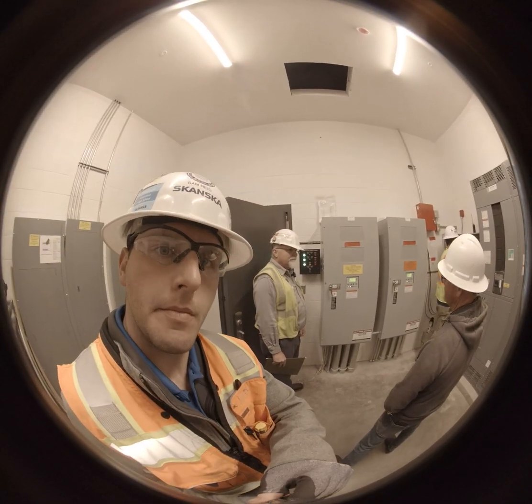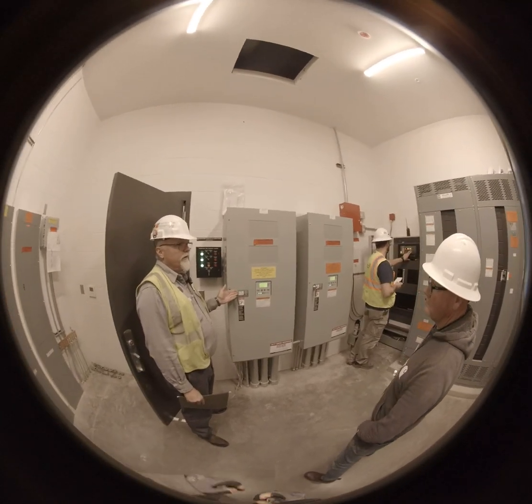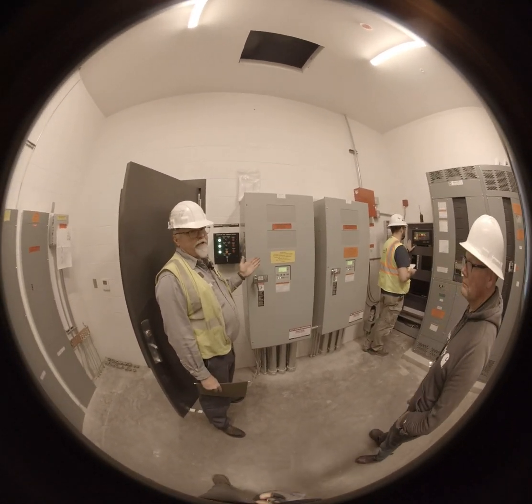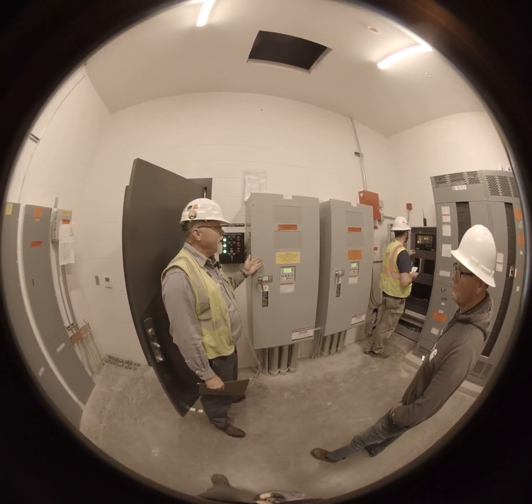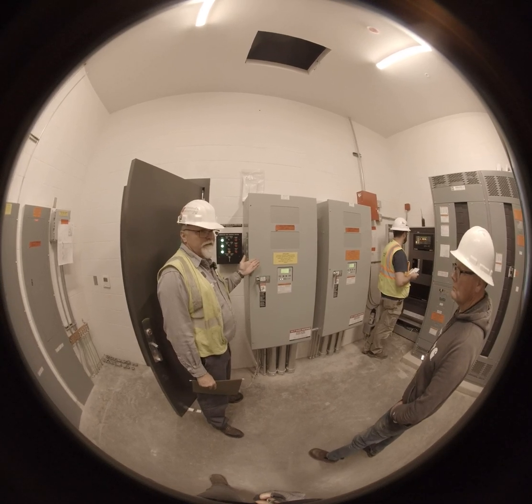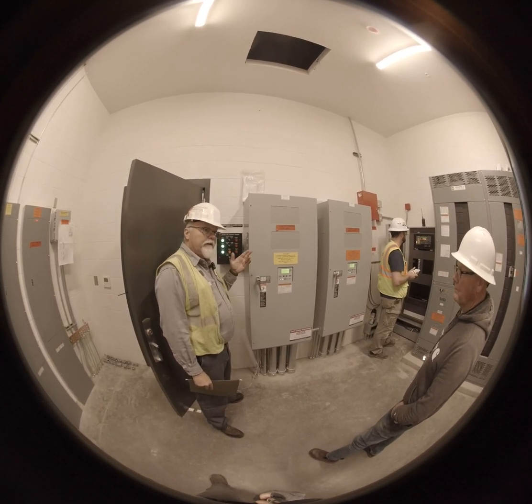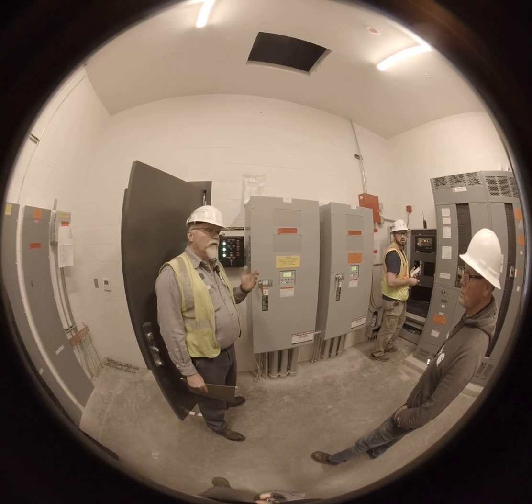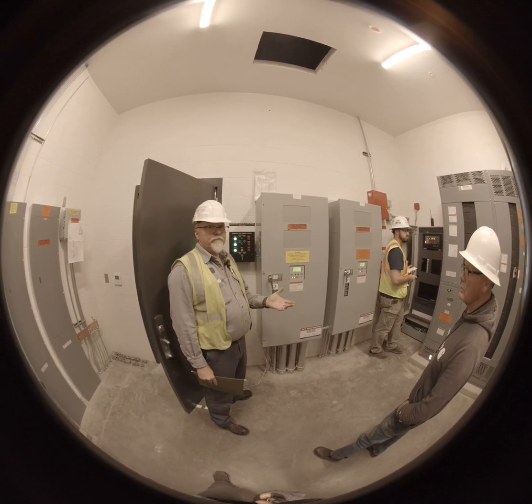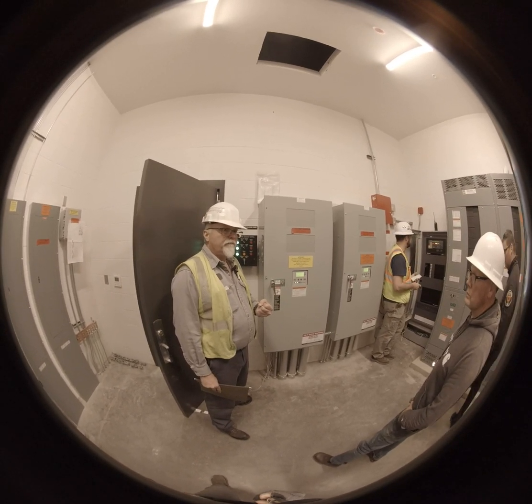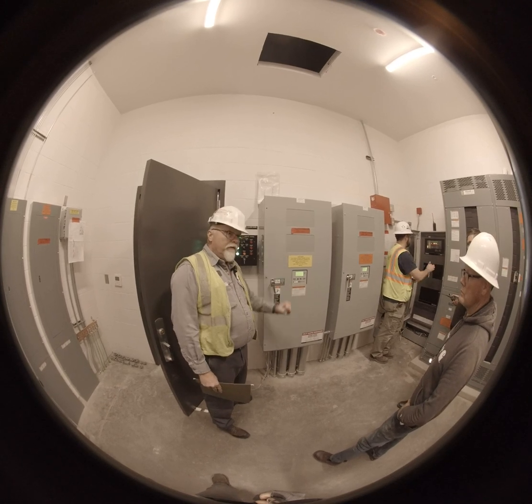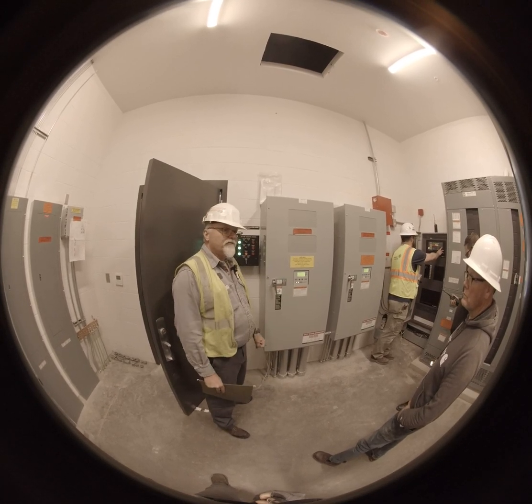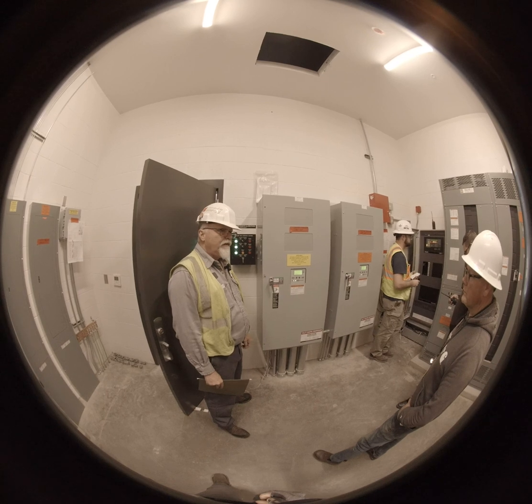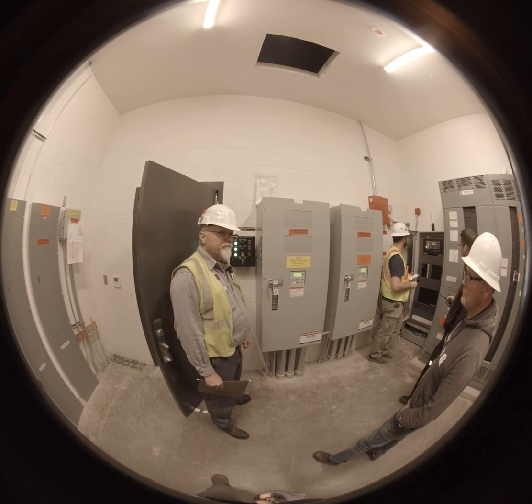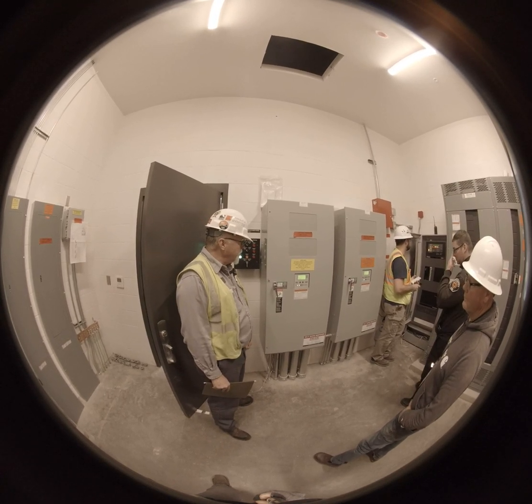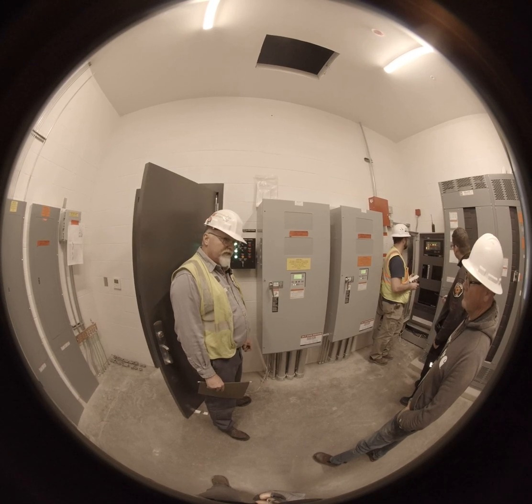And of course, the third way of doing this would be to open the breaker that is feeding the utility side of this transfer switch. Typically, they'll do that with the fire marshal here, or the authority having jurisdiction. They open that up and watch the timing on it to make sure it makes that 10 seconds. Make sense? Yep.